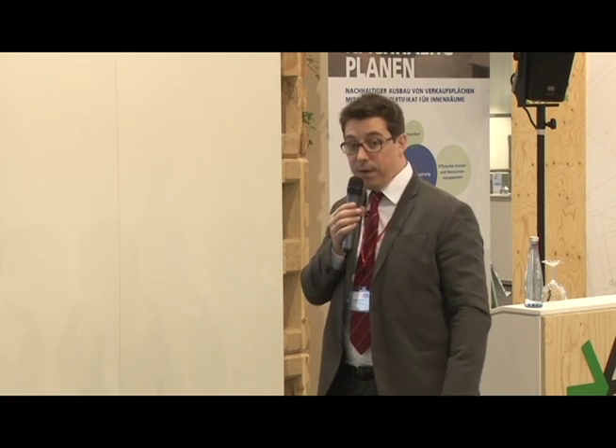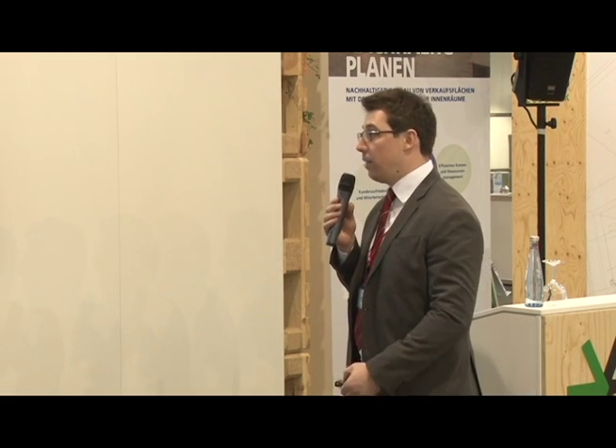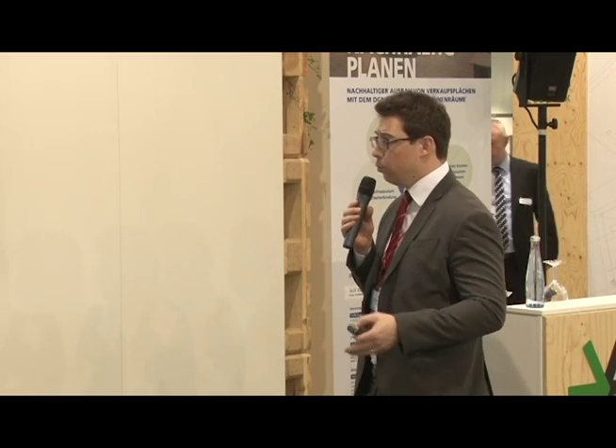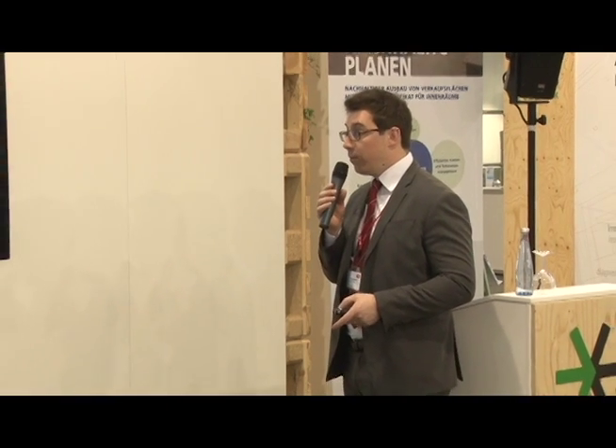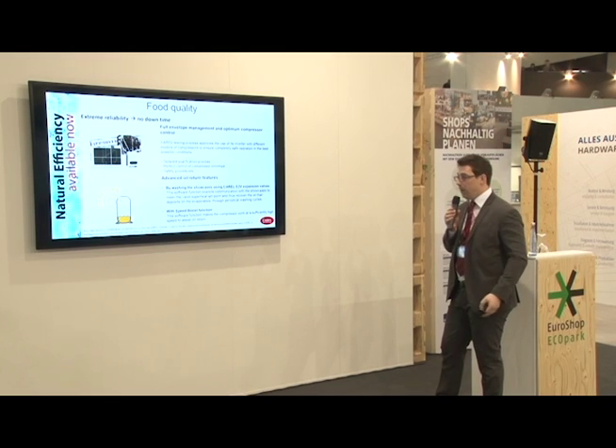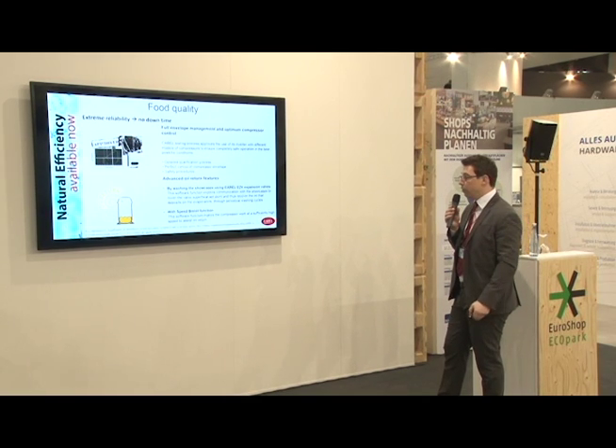Food quality is the third pillar. Extreme reliability means no downtime — we reduce the time where the unit is off, because we fully control the operating envelope of the compressor. We have certified all the BLDC compressors that we are offering in our DC inverter, and thanks to this detailed qualification process, we can perfectly control and let the system work with extreme reliability. Moreover, not just control of the compressor itself with the envelope, but also control of oil return with specific features — like the washing of the showcases, opening the expansion valves and trying to return all the oil lost in the cabinets by increasing the speed of the compressor.